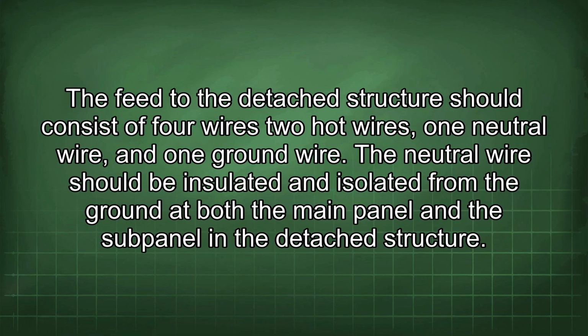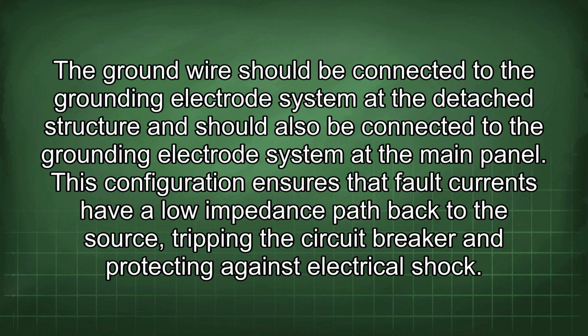The feed to the detached structure should consist of 4 wires, 2 hot wires, 1 neutral wire, and 1 ground wire. The neutral wire should be insulated and isolated from the ground of both the main panel and the subpanel in the detached structure. The ground wire should be connected to the grounding electrode system at the detached structure and should also be connected to the grounding electrode system at the main panel.